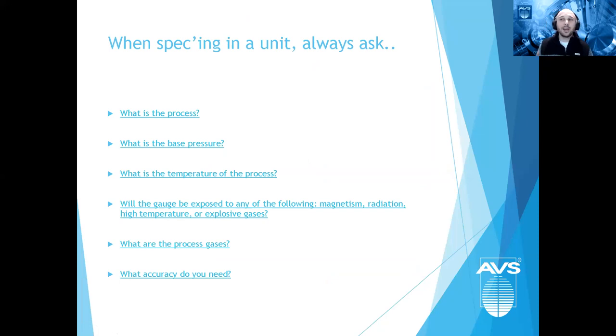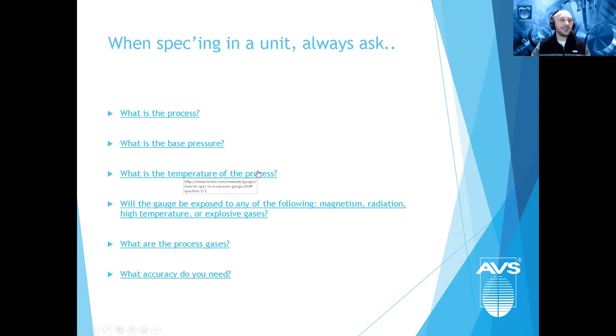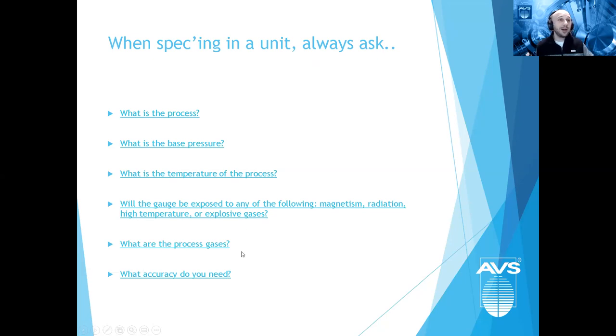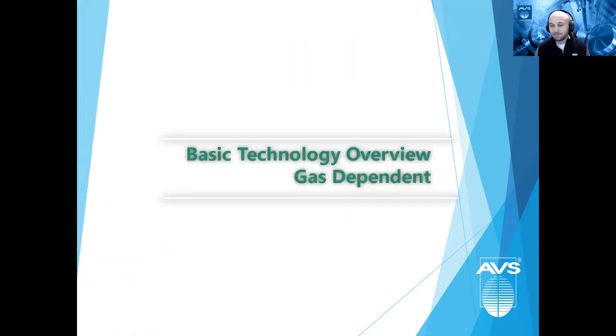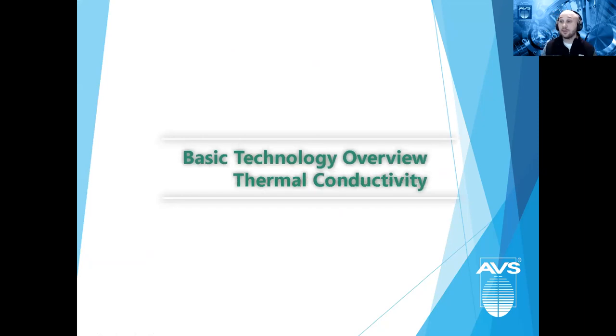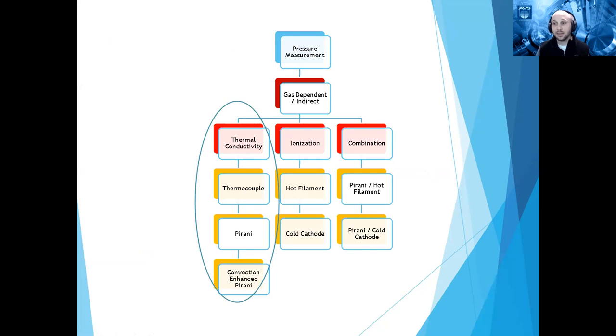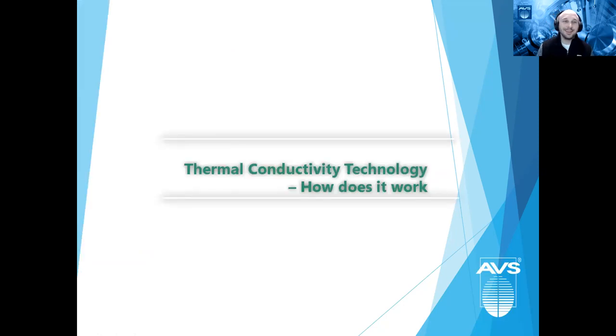Before getting into any technology, I always like to ask these basic questions when speccing something in: What's the process? What's the base pressure? What's the temperature? What will the gauge be exposed to internally and externally — magnetism, radiation, high temperature? Do I have explosive gases where a heated filament is a no-go? What are the process gases? Do I need to worry about corrosion, acidic, or basic vapors? And what accuracy do I need? From these questions, I'm pointed to the right gauge.